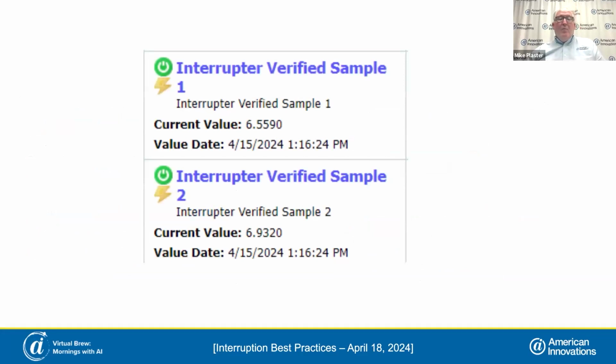All right. What if you should see interruption verification where you get 2 on readings? That's usually an indication that your unit has not started interruption. We have sent the command to the unit to say, hey, I want you to start interrupting right now, but there could be a problem with the relay, the wiring, or some setup that's keeping it from interrupting. So our verification comes back with 2 on readings rather than an on and off.